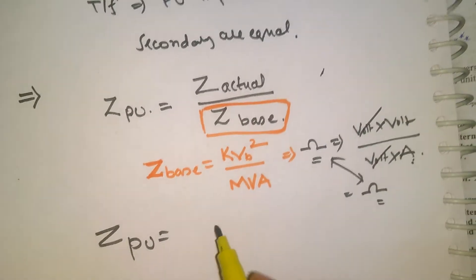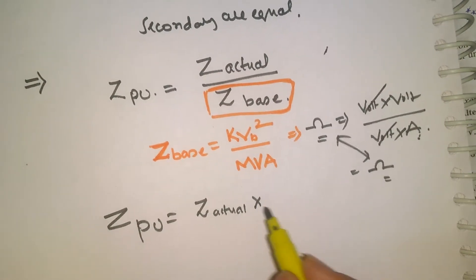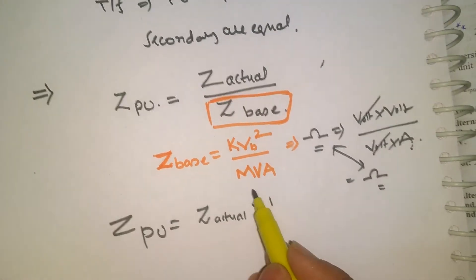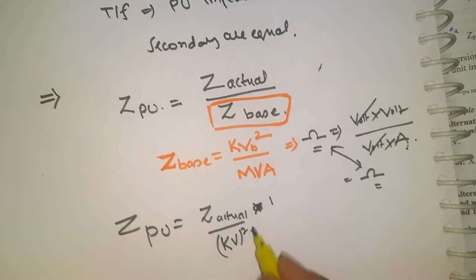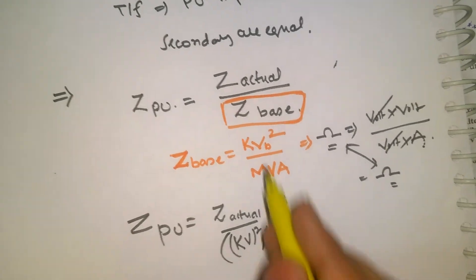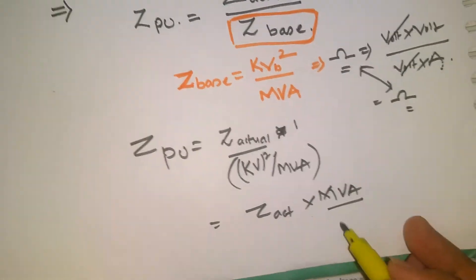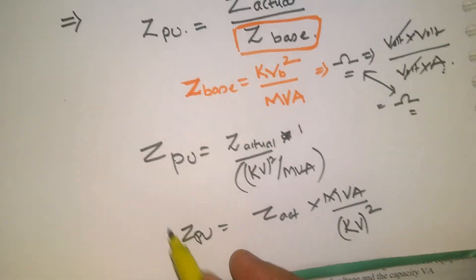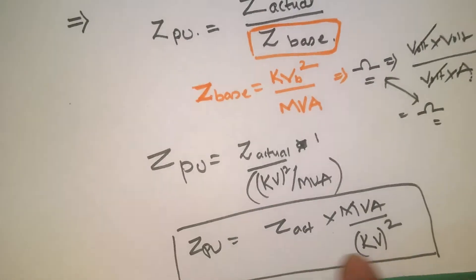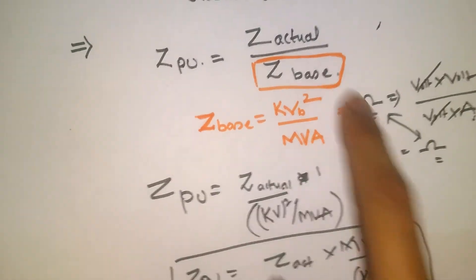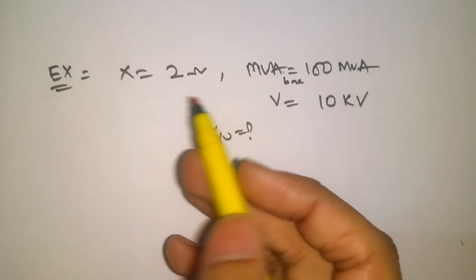The overall formula for Z per unit is Z actual divided by Z base, where Z base equals KV squared divided by MVA. So Z per unit equals Z actual times MVA divided by KV squared. Just make a note: Z per unit equals Z actual divided by Z base, and Z base equals KV squared divided by MVA. Now let's solve one example based on this.